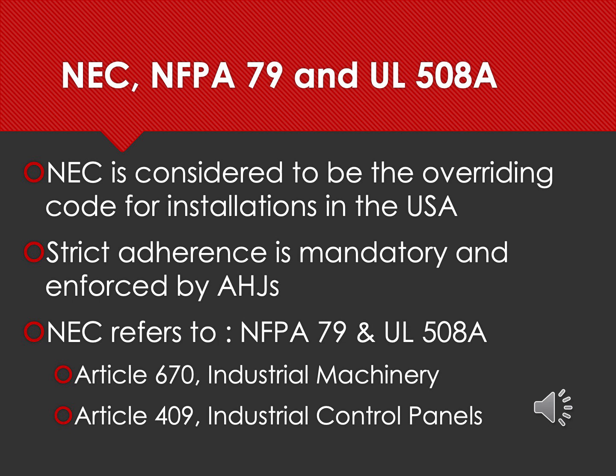As most of you know, NEC is deemed to be the overriding code for the installations in the United States, and again, it's legally recognized as state of the art. Strict adherence to NEC is mandatory as the equipment cannot be put in service in the states without the approval of authorities having jurisdiction, also called AHJs. Article 670 in NEC refers specifically to industrial machinery requirements, which in turn refers to NFPA 79 for additional information and clarification needs. Further, Article 409 in NEC refers to industrial control panels codes, which references UL 508A standards.